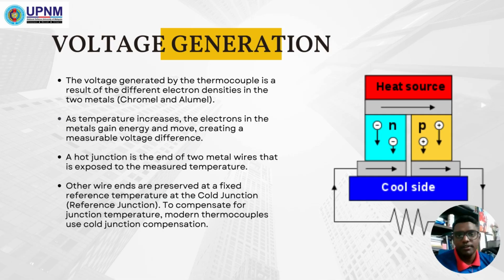Another thing in thermocouple type K is voltage generation, which is one of the most important things. The voltage generated by the thermocouple is a result of the different electron densities in the two metals, which are chromel and alumel. As temperature increases, the electrons in the metals gain energy and move, creating a measurable voltage difference. A hot junction is the end of two metal wires that is exposed to the measured temperature, and the other wire ends are kept at a fixed reference temperature at the cold junction, which is called a reference junction. So this is for voltage generation.